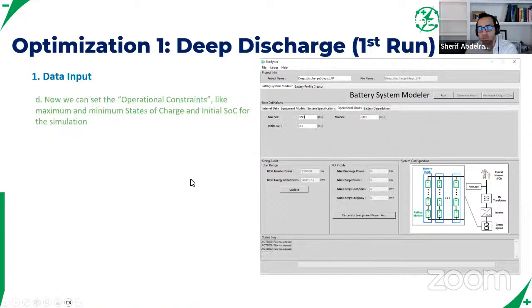Then you start to set your operational limits for your system. One of the things I wanted to touch on that you really learn through operation is that the burden of energy management between battery racks that are placed in parallel is very sophisticated. It is not currently 100% figured out in the industry.